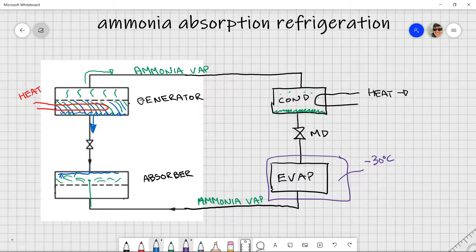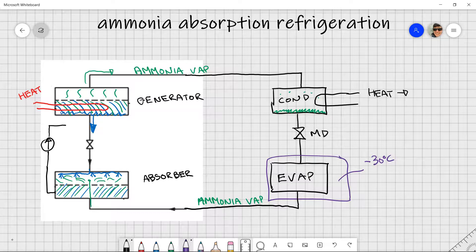Now generally what we want to do is spray it in so it can mix with the ammonia vapor that's in there and absorb it at the most efficient manner. And then what we're left with is down at the bottom, we've got now ammonia that's mixed with a water solution. And so we now have lots of ammonia that's in that solution and we would take a little pump and we would pump it up and add it into my upper vessel.